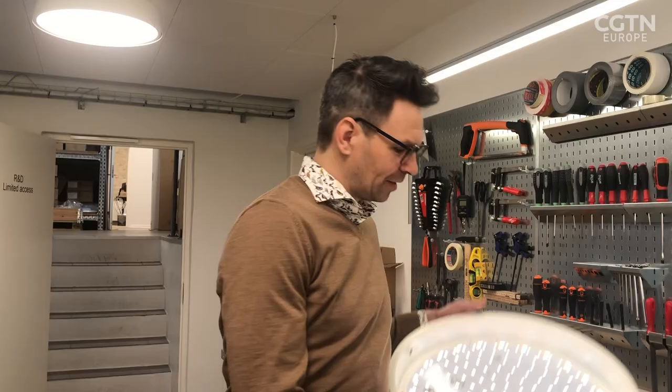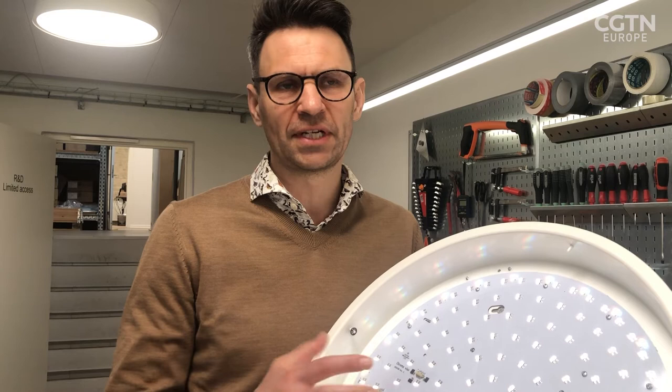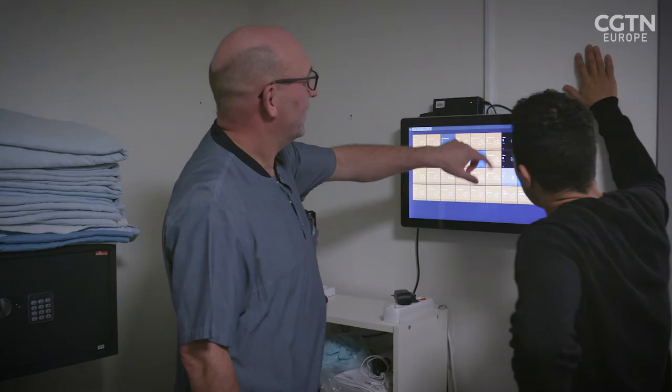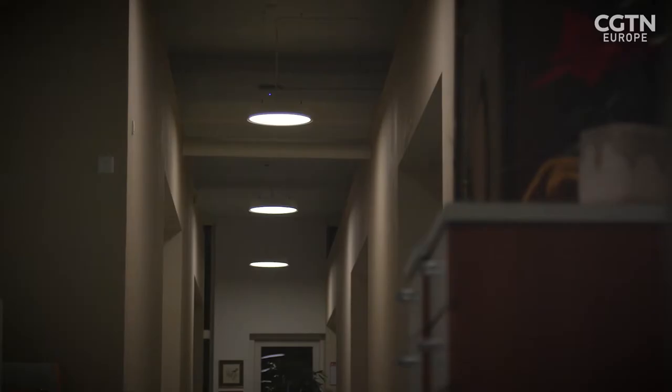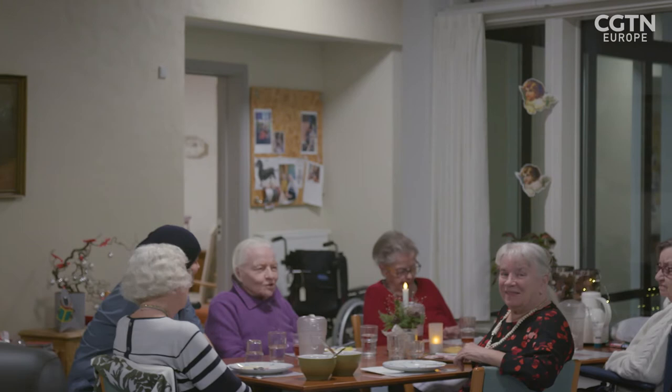So how is this lighting system different from the ones in the rest home? Basically, under the hood, it's still the same bits and pieces — we also use six different types of LEDs to construct whatever kind of color and spectral composition. But the big difference is in the programming of the luminaire. With ergonomic lighting, we use colored lighting as the general lighting in operating theatres, whereas in the nursing homes we applied different shades of white — not to improve work conditions, but to improve fundamental health conditions.